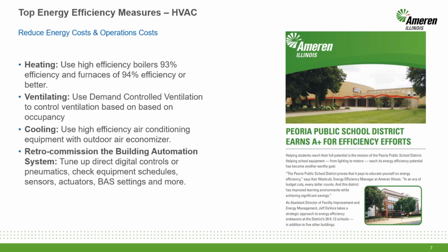Now, these CO2 sensors do need to be replaced at some time, so it does add some maintenance, but we still recommend demand-controlled ventilation. And COVID has spurred the adoption of ultraviolet light air purifiers, which can reduce energy by cleaning the air and reducing the use of unconditioned ventilation air, and this can be combined with demand-controlled ventilation. Currently, the state of Illinois is offering some CURA grants, and I know some of the major control companies are working with municipalities to apply and use grant funds for air purification.